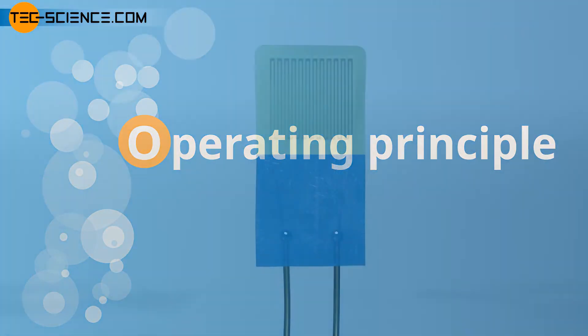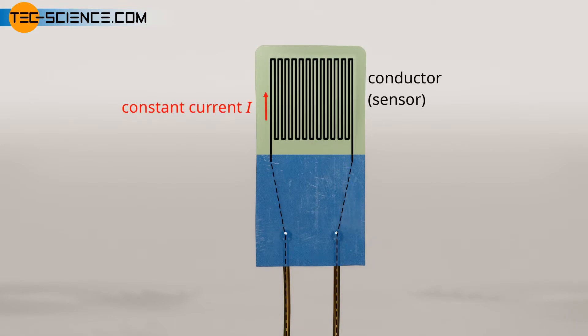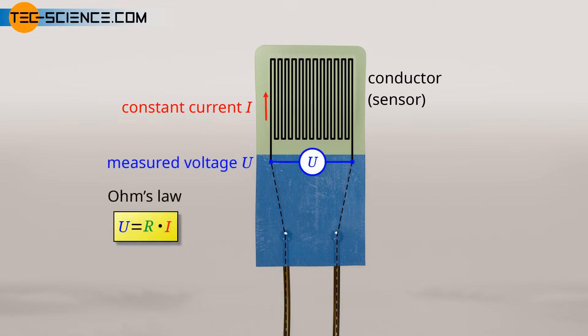Operating principle. In resistance thermometers, a constant electrical current flows through a conductor which serves as the sensor. The currents are usually less than 1 milliampere to avoid excessive heating by the current. According to Ohm's law, at a constant current the voltage at the measuring conductor varies depending on the electrical resistance and thus on the temperature.